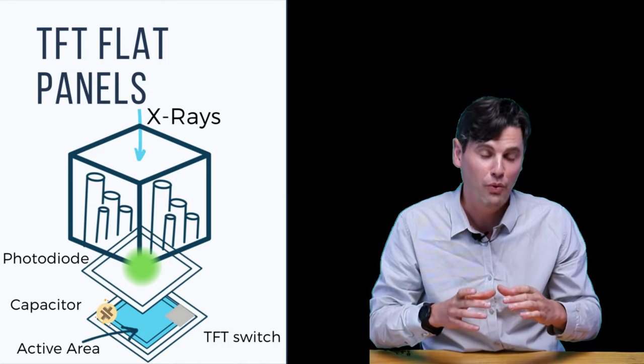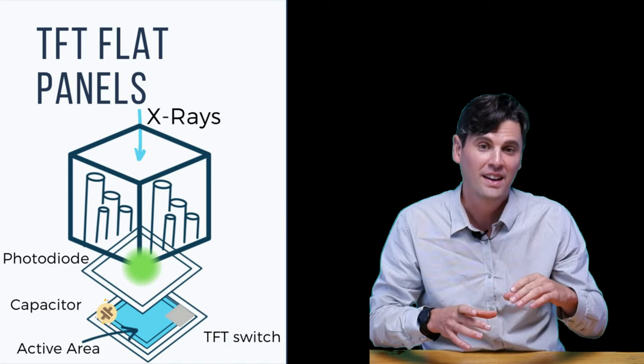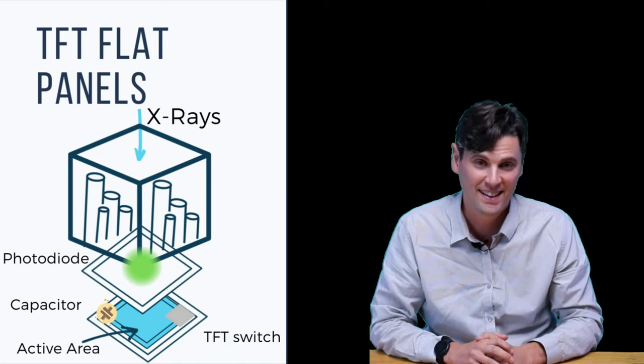TFT arrays are actually the same technology used in flat panel displays. In flat panel displays, the individual addressing of each element is used to turn pixels on and off — here we use the same principle to read out detector signals.